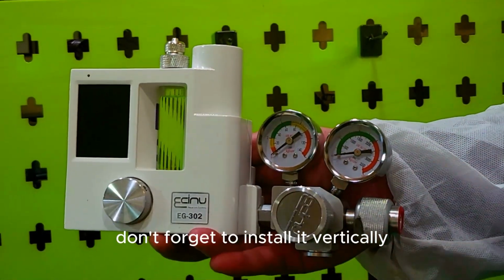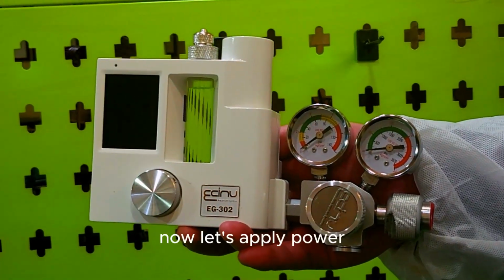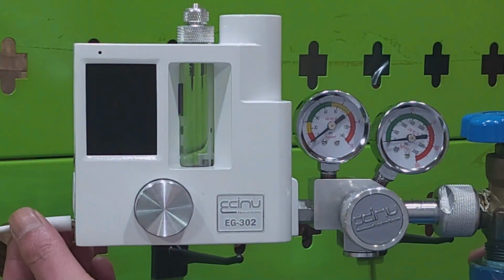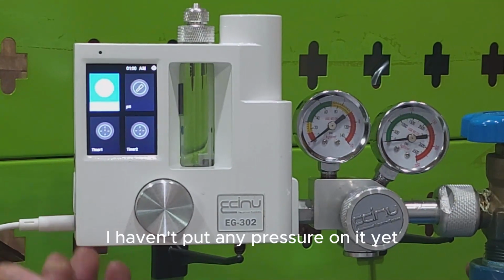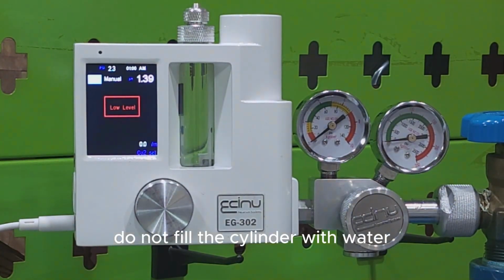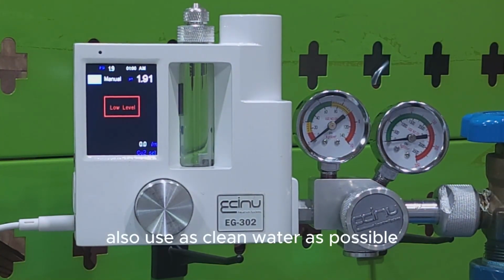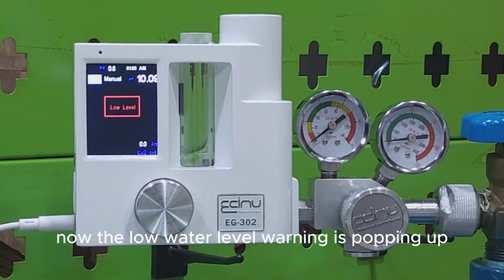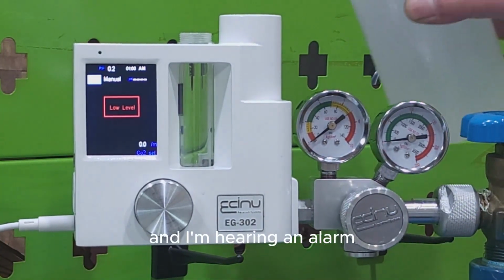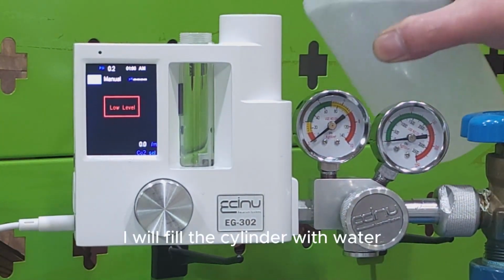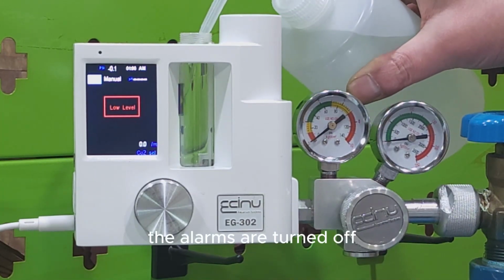Don't forget to install it vertically. Now let's apply power. I haven't put any pressure on it yet. Do not fill the cylinder with water. Also, use as clean water as possible. Now the low water level warning is popping up and I'm hearing an alarm. I will fill the cylinder with water. The alarms are turned off.